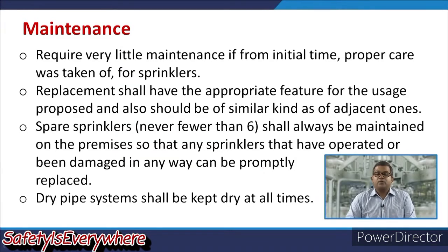Replacement shall have an appropriate feature for the uses proposed and also should be of a similar kind as the adjacent one. Spare sprinklers, never fewer than 6, shall always be maintained on the premises, so that any sprinkler that has operated or been damaged in any way can be promptly replaced. So this is again a standby arrangement for the sprinkler system. Dry pipe system shall be kept dry at all times. This is the mandatory requirement and it is part and parcel of your maintenance protocol.